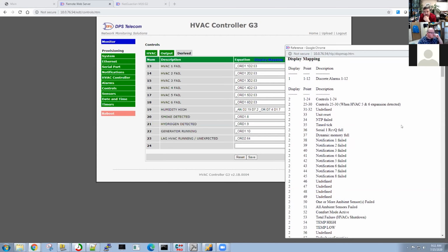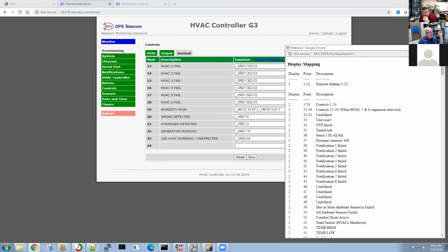So if we decode those, what's 1.1, alarm point 1? Yeah, 1.1 is a discrete alarm point. So if we saw a short on the first pair, labeled HVAC fail alarm. That's self-reported from the unit. Yeah, if HVAC 1 has a discrete alarm output indicating some kind of error state, we bring that over to the 66 block, informing us: hey, I'm your far end unit, I can't run for whatever reason, don't try to run me. Then that would come in and trigger this.